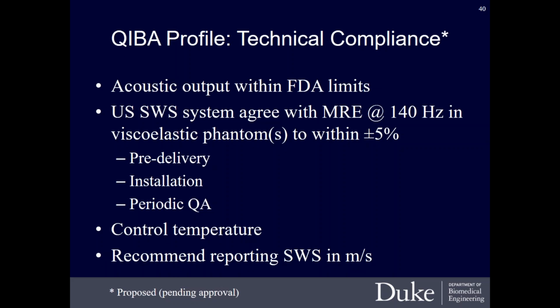So starting to touch on what the QIBA profile is trying to achieve now to ensure some better standardization in the community. Right now the QIBA profile from a technical perspective, and all of this is still a work in progress, so this is not set in stone yet, though there will be soon a public version of the profile available for comments, is that all acoustic output for these systems remain within FDA limits. That's primarily on the acoustic radiation force side.